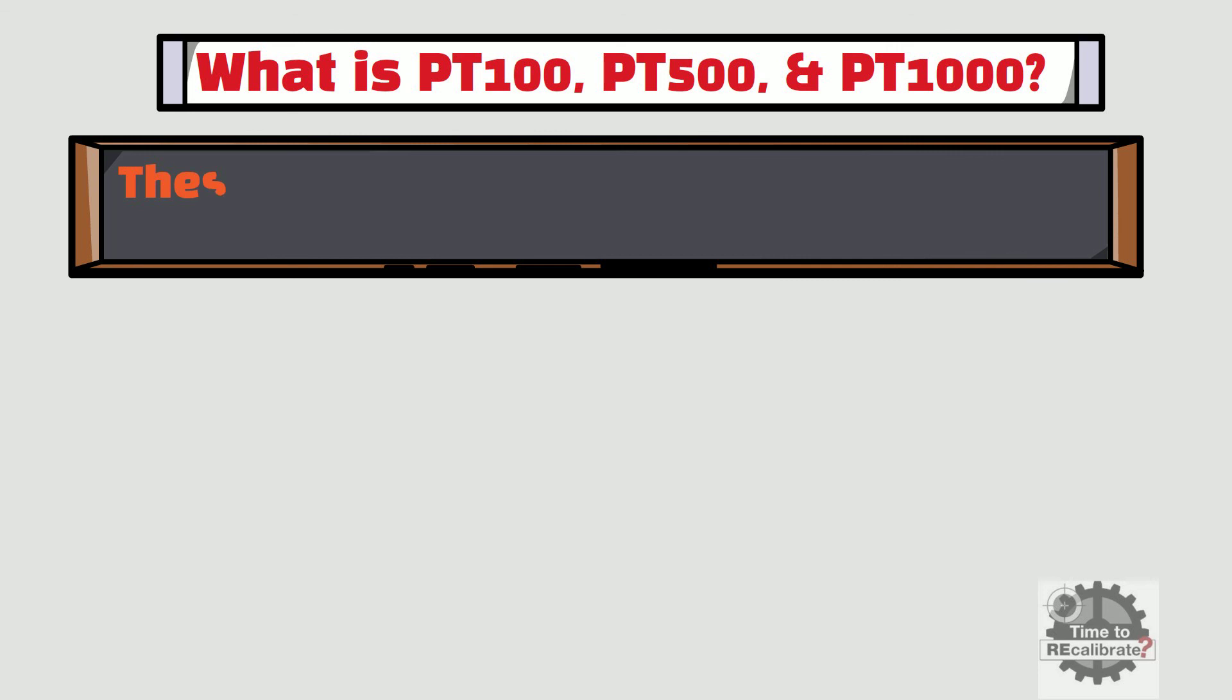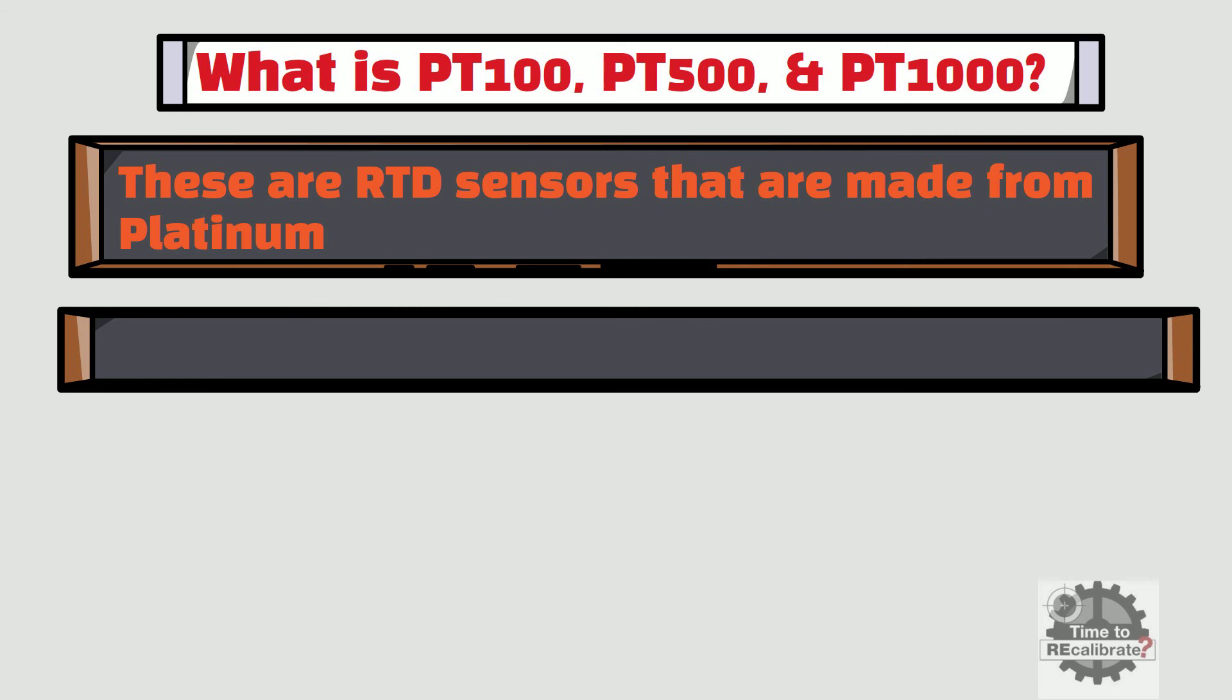Let's learn what PT100, PT500, and PT1000 are. These are all types of RTD sensors that are made from platinum. The PT100 sensor has a resistance of 100 ohms at 0 degrees Celsius and is by far the most common type of RTD sensor.